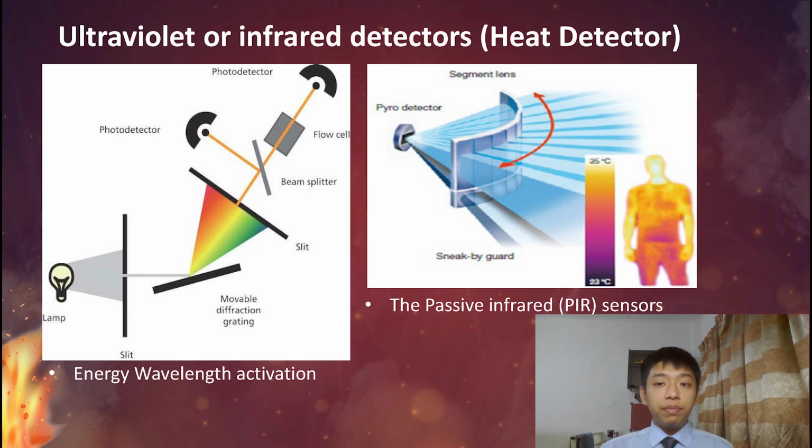Commonly, a beam splitter is included, directing part of the light to another photodiode. This configuration allows the electronics to make correction for fluctuation in the lamp intensity and thus improve the optical performance of the instrument.